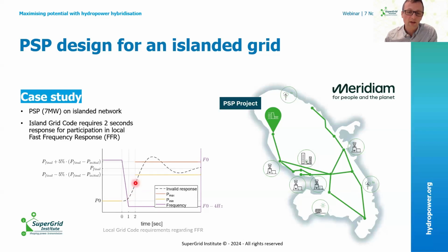As you can see here, the response of a Pelton, for example, would not be satisfying because it doesn't enter the required bands within the 2 seconds. Besides, it overshoots, so it gets out of the band after that. So these fast frequency response mechanisms are quite stringent and can be challenging for hydropower schemes. And it was the case for the pumped storage power plant that Meridiam had been working on for the last 7 years. It's a 7 megawatt pumped storage scheme, and it was struggling a bit to make the case to the regulator.